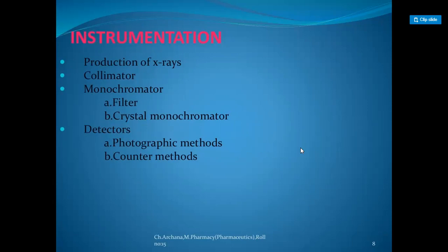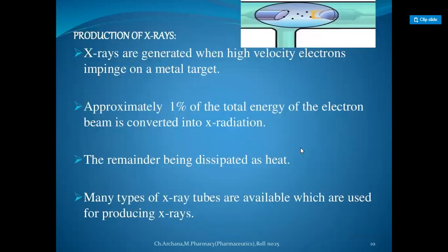In instrumentation, the system contains an X-ray source, collimator, monochromator, and detectors. X-rays are generated when high velocity electrons impinge on a metal target. Approximately one percent of the total energy of the electron beam is converted into X-radiation, with the remainder being dissipated as heat. Many types of X-ray tubes are available for producing X-rays.